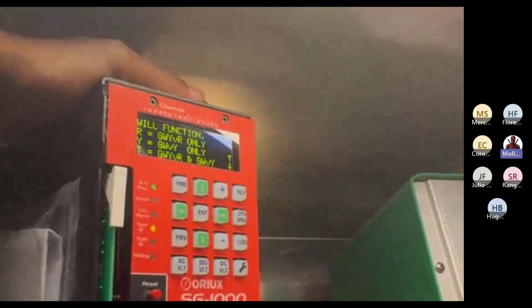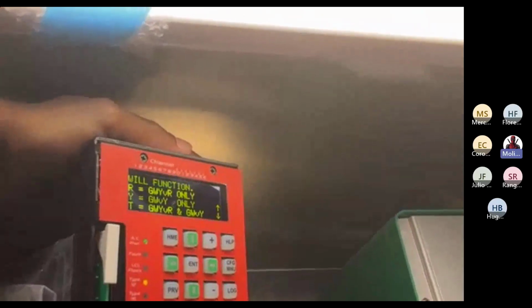A lot of this stuff, if you kind of know traffic, you don't really need to check the manual. It's kind of right here. With the standard T, it's only checking the green walk yellow versus red and green walk versus yellow. That's the default, like vehicles multi-indication.